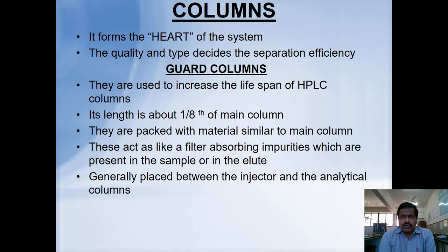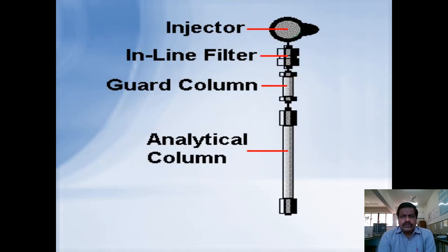The guard columns used match whichever column is being used for separation. For example, if you are using a reverse-phase C18 column, then a reverse-phase C18 guard column is also available. The guard column is approximately one-eighth the size of the main column and is packed with a material similar to the main column. It acts as a filter, absorbing impurities present in the sample. The guard column is placed between the injector and the analytical column.